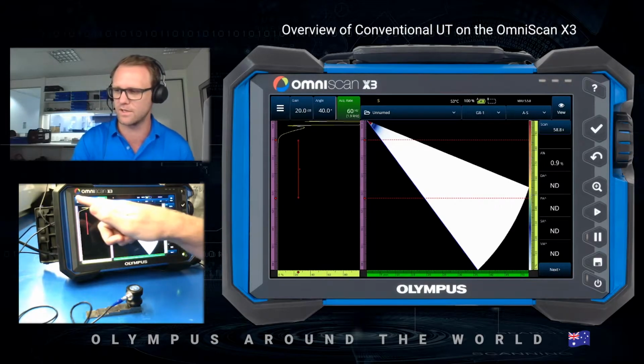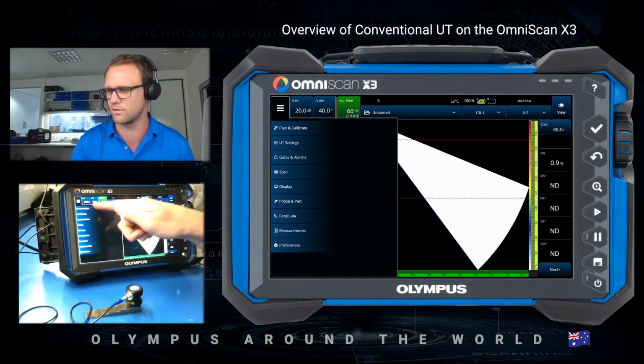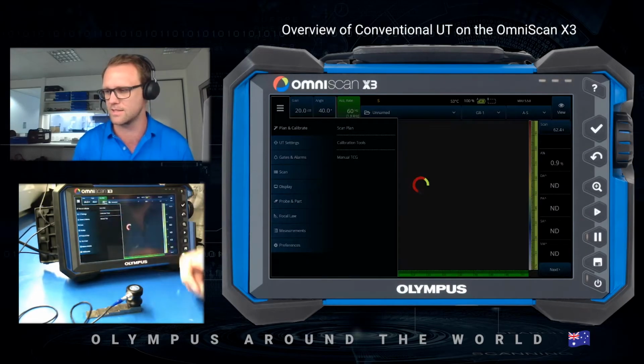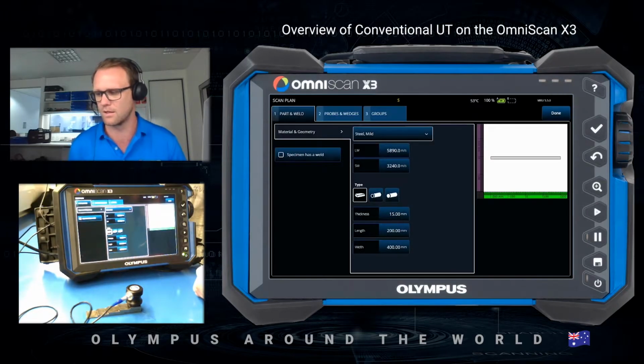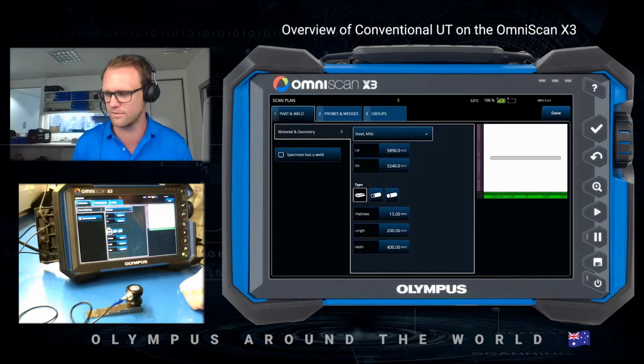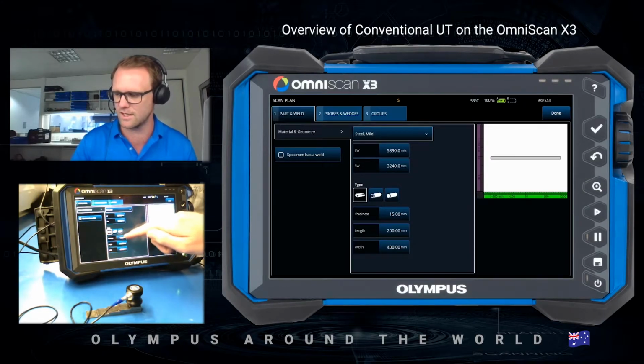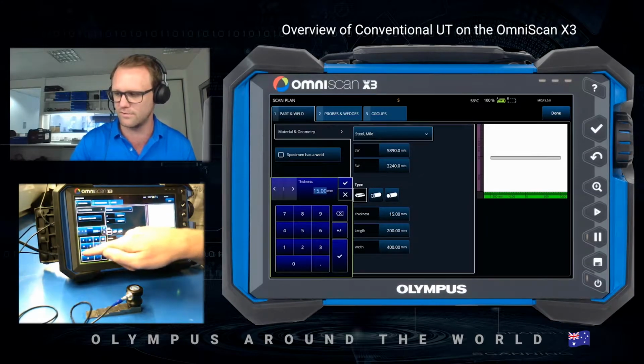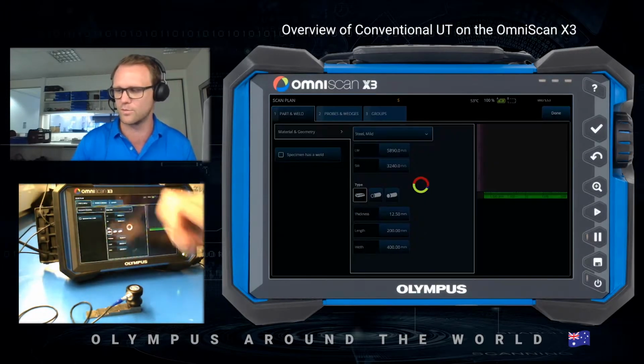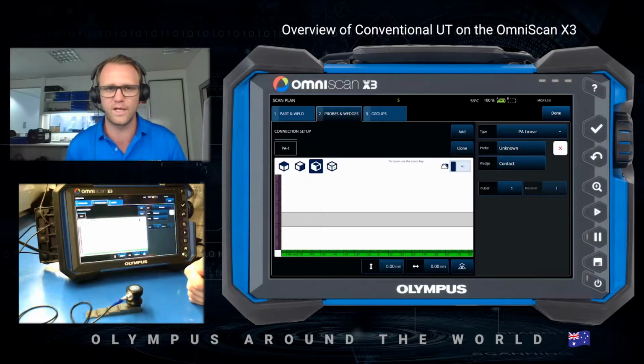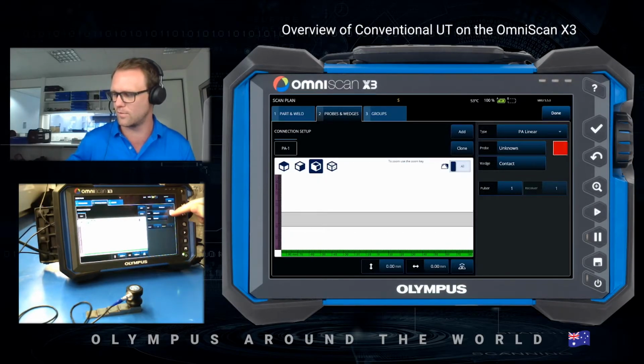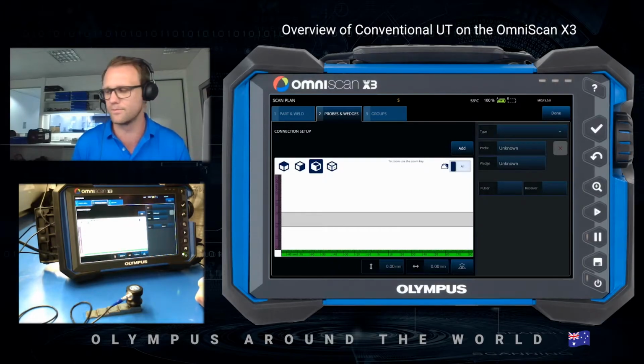So to get started, we're just going to access the burger menu up the top left corner of the screen, plan and calibrate, and then scan plan. The first setting is the same as if you were doing a phased array setup. I'm just going to choose the thickness and set it to 12.5, as that is the max thickness of my step wedge. Then go into probes and wedges. From here, the default setting is to use a phased array group, and so I need to remove that by pressing the X and delete.